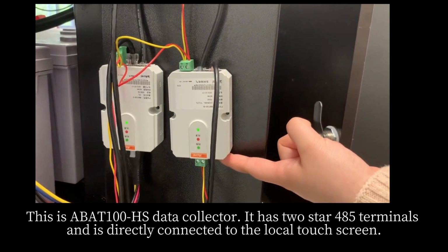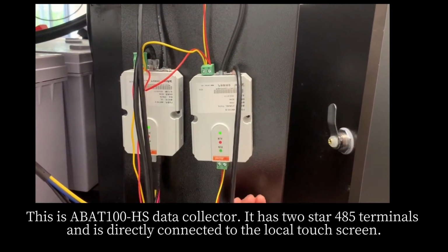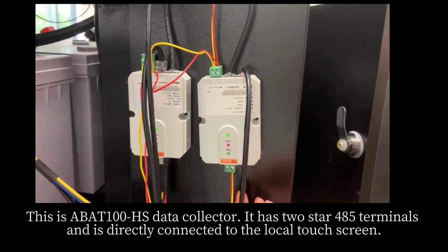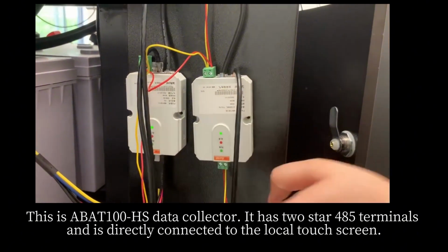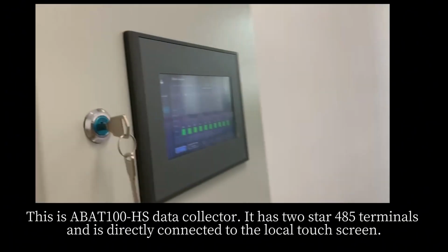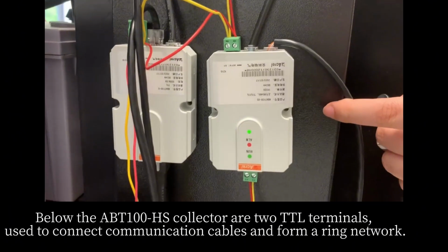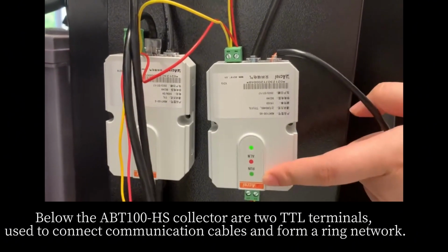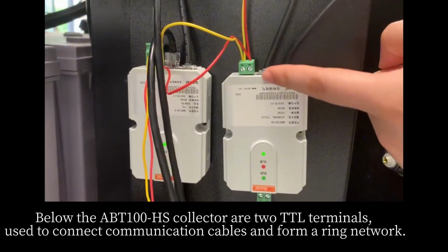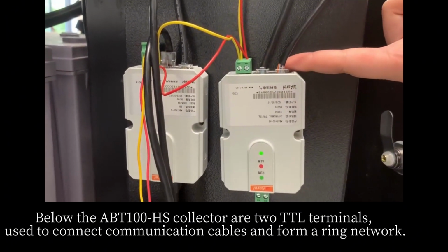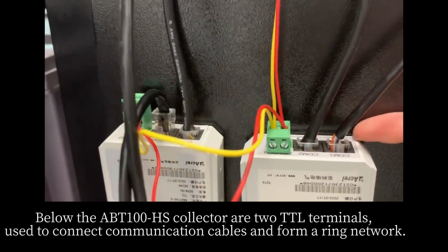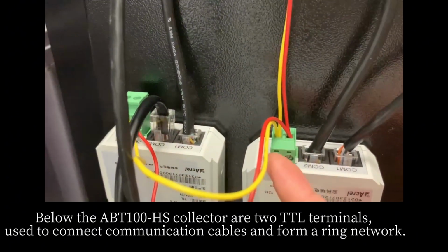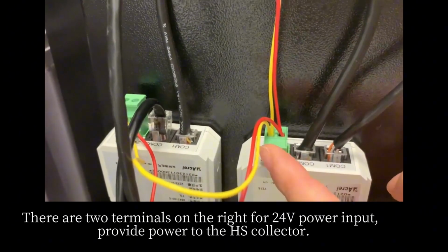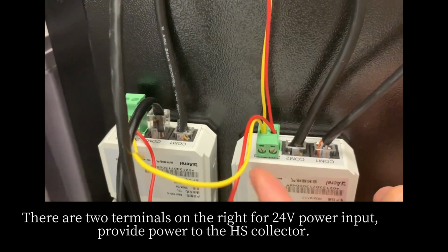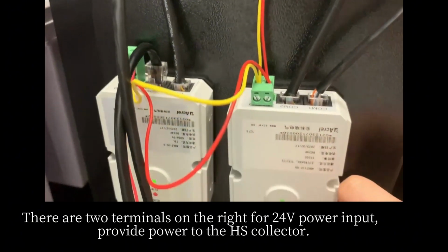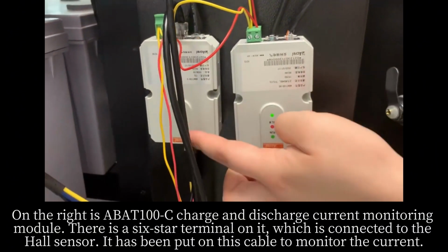This is the ABAT100-HS data collector. It has 2 RS485 terminals and is directly connected to the local touchscreen. Below the ABAT100 collector are 2 TTL terminals used to connect communication cables and form a ring network. There are 2 terminals on the right for 24-volt power input, providing power to the HS collector.